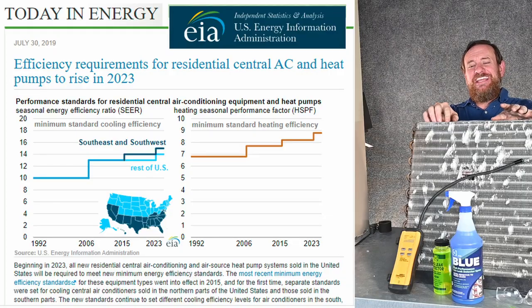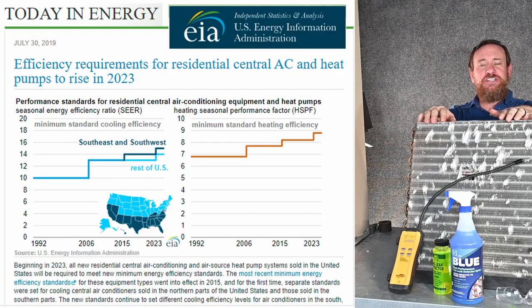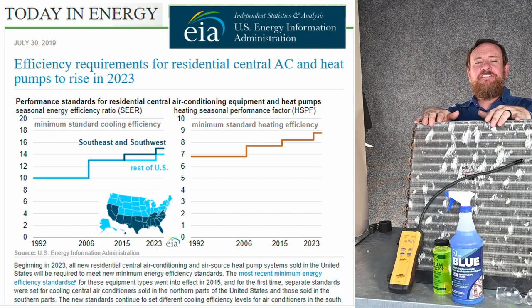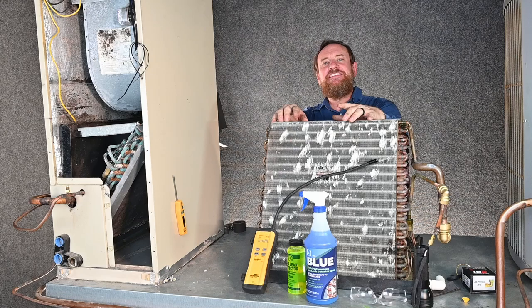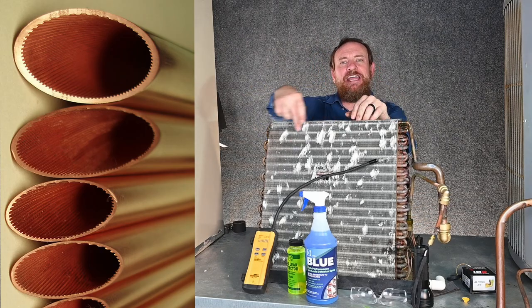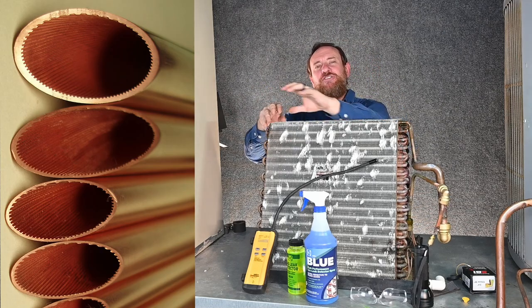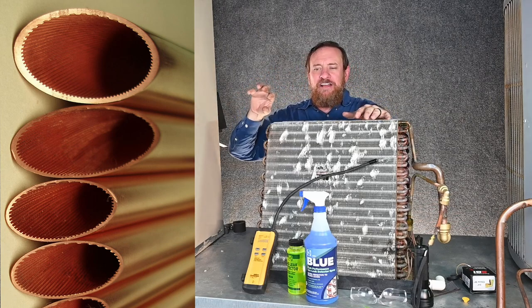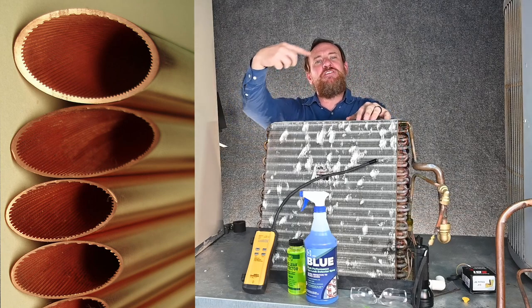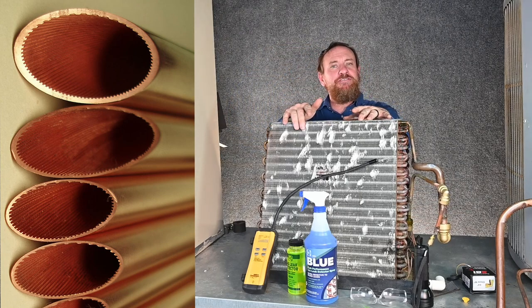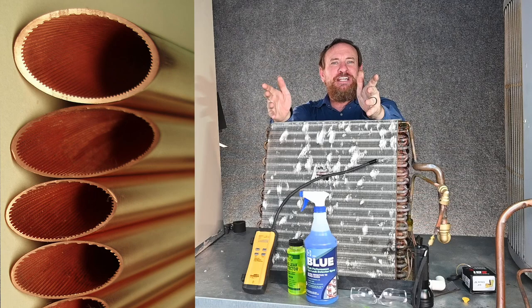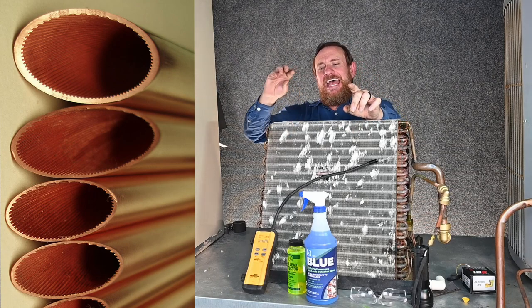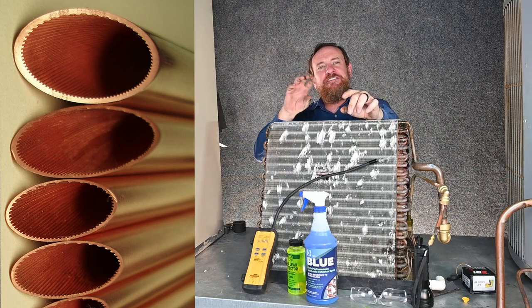Another factor is efficiency. To make these systems more efficient — more heat transfer in a small enough space to fit in a closet — manufacturers do things like rifling, where they take the tubes running back and forth and mar the inside so the refrigerant spins as it travels through. That rifling effect means more refrigerant is touching more tubing, giving better thermodynamic properties and better heat transfer.